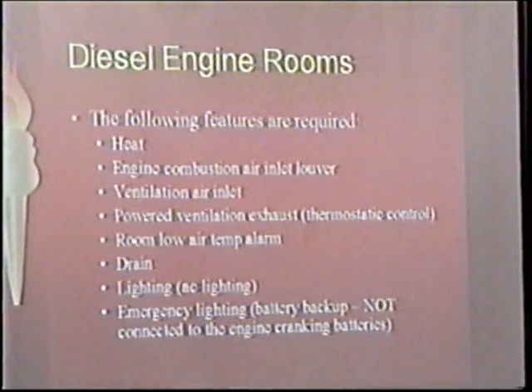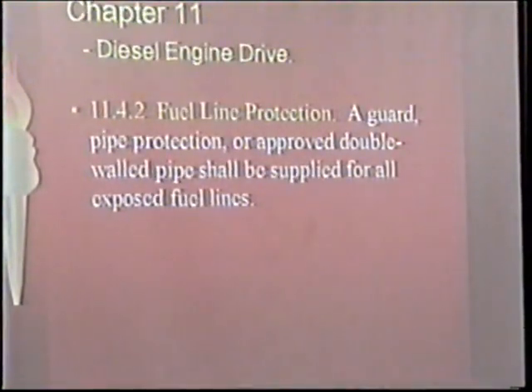So from the alarm standpoint, we need to coordinate with the controller to see if it is set up to provide that alarm. Right. Because if we don't have it on the controller, then as the alarm contractor, you should provide the thermostat for that. And the thermostat setting requirement in NFPA 20 is that it should be set at, I think, 45 degrees.